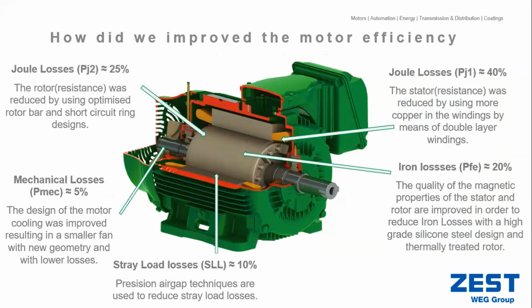First, we look at the stator. The Joule losses in the stator make up about 40% of the losses in a motor. One way to reduce that loss is by adding additional copper into the windings, which means going for a double layer. The more copper you have, the lower the resistance.